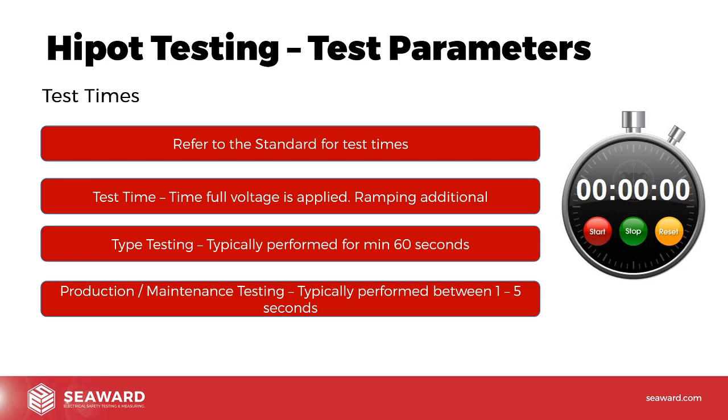eaten into the total hold test time. So you have ramp times and you have hold times, and those are two separate things. So your total test time should consist of hold time plus ramp times that you add. Your hold time is the important one because the product should withstand for the period stated within the test standard. So if you do add ramping, that needs to be in addition to the hold time within the test standard.